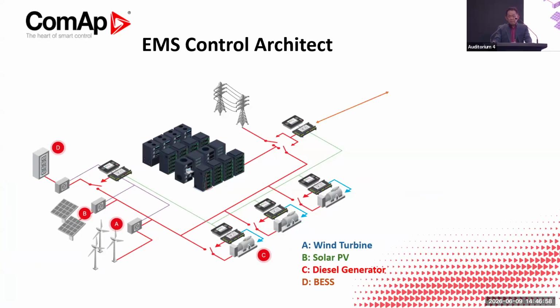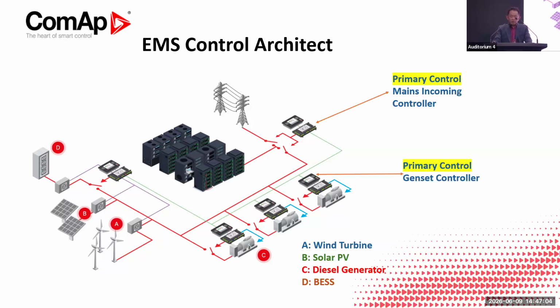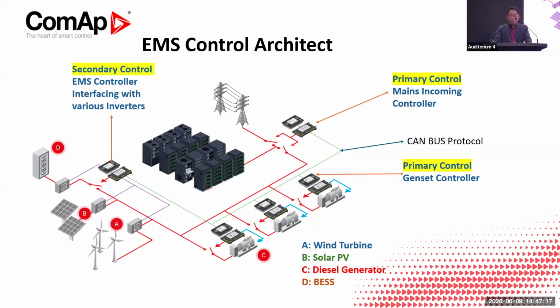We have the mains controller, which is also known as the primary control, and then the genset controller, another primary control. Then we have the secondary control, which is the EMS controller. You can see on the green line, this is the internal CAN bus protocol where different controllers communicate.